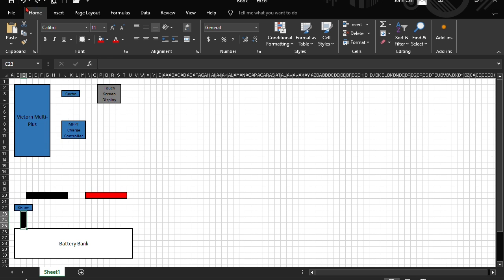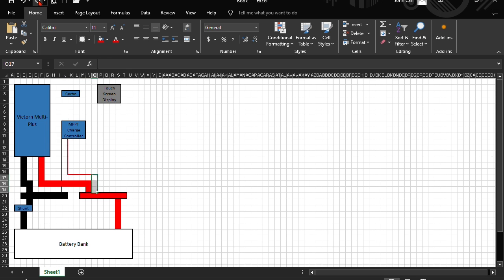We're going to put a 2-aught cable between the battery and the shunt, and again a 2-aught cable between the shunt and the bus bar. We'll pull 2-aught cables between the multi-plus and the bus bar on the power side, and then a 2-aught cable between the bus bar and the battery. Moving to the MPPT charge controller, we'll pull an 8 or 10 gauge wire from the MPPT charge controller to the bus bar, charging the battery. This way you're charging the battery through the shunt, so the shunt can monitor what kind of power is coming and going.